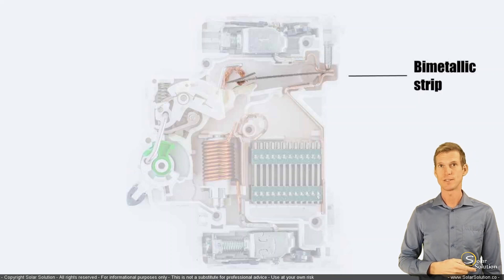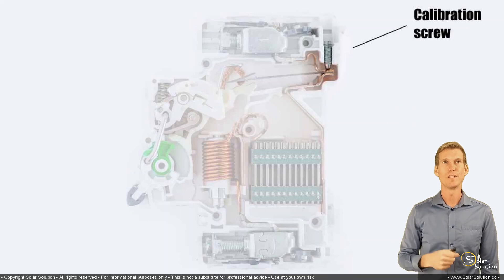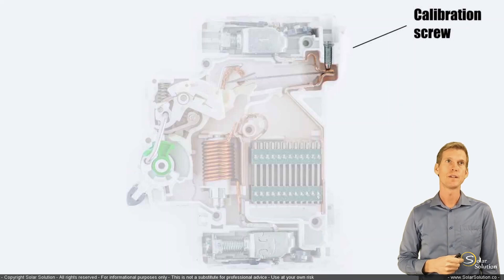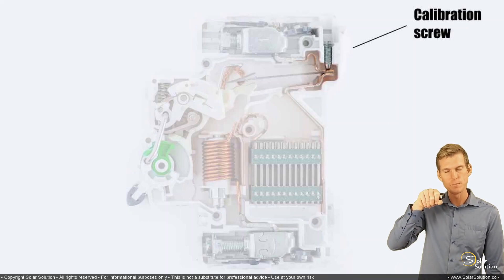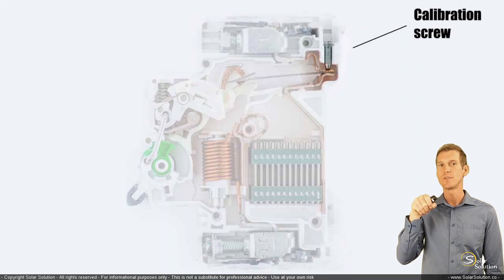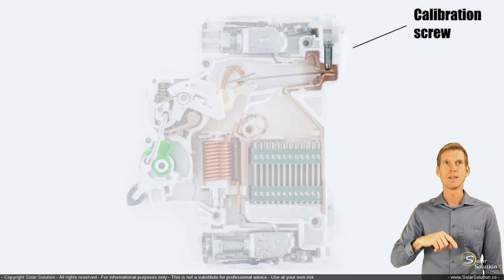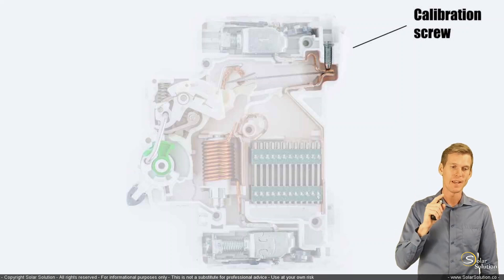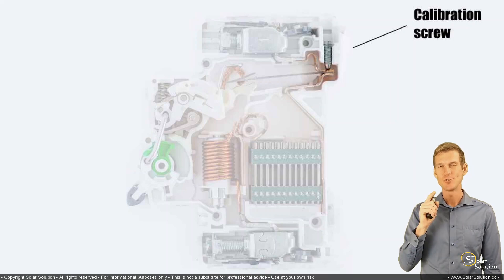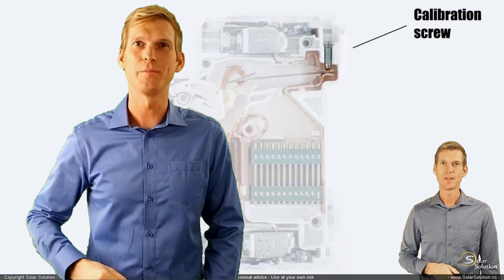Most breakers have a calibration screw, normally at the top, used to fine-tune at which point the bimetallic strip will open or close the circuit based on the slow tripping current. This calibration screw is set in the factory and you should not touch it.